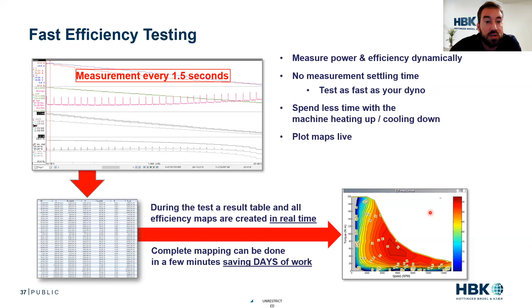This cycle detect, more of a unique aerospace thing, allows us to very accurately measure power for high fundamental frequencies. A lot of times we're pushing the machines very quickly, operating at 800 hertz, 1 kilohertz, 2 kilohertz fundamental. Where many tools that measure power were intended for the grid, 50 or 60 hertz, our cycle detect algorithm allows us to measure electrical power very accurately even at high speed. We can measure fundamentals in the kilohertz range and track power accurately even if the fundamental is shifting.